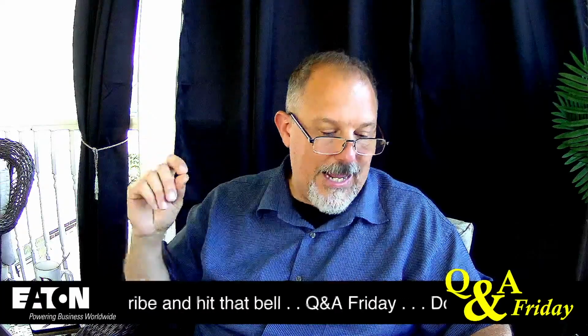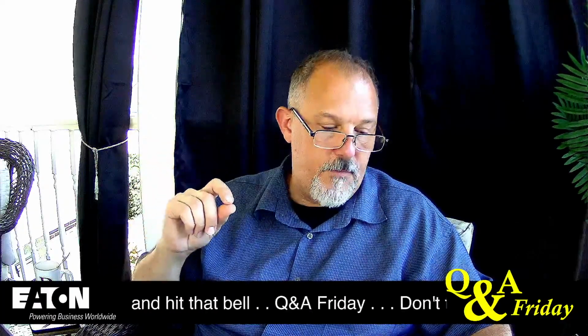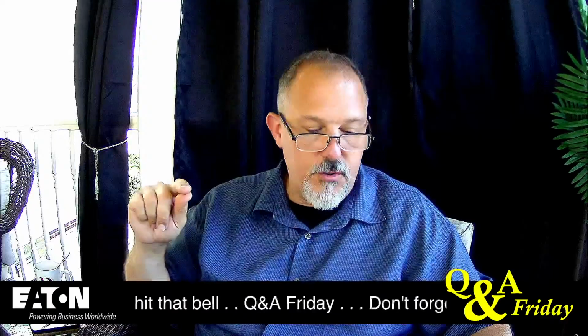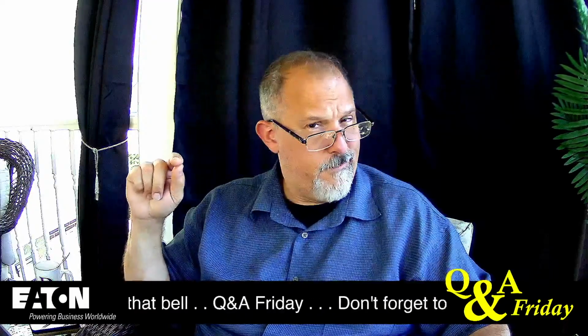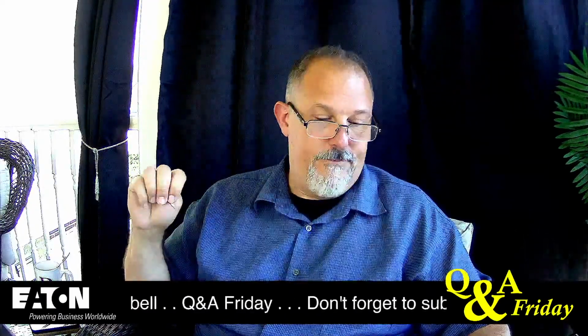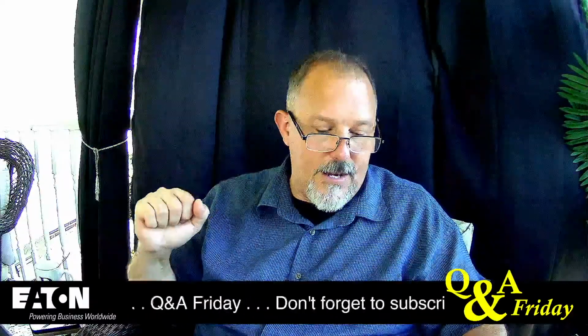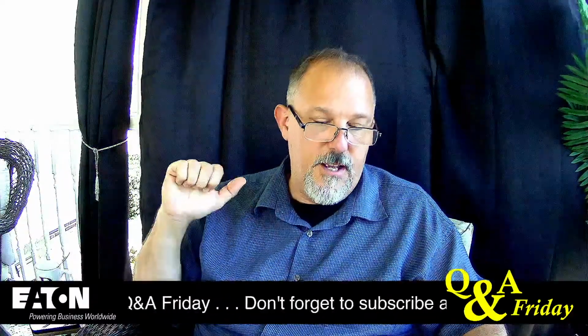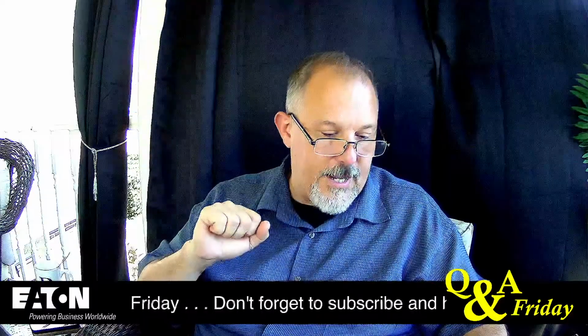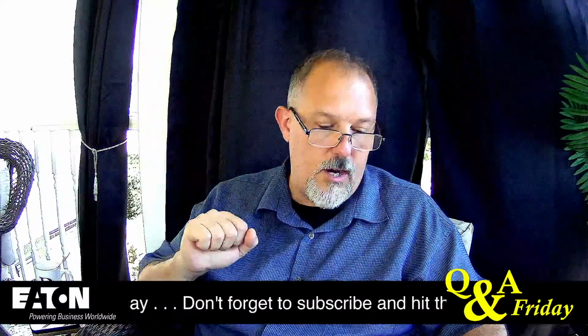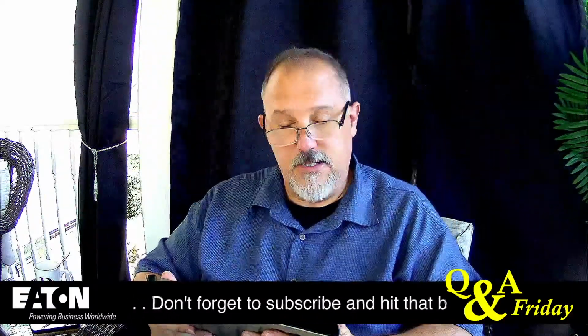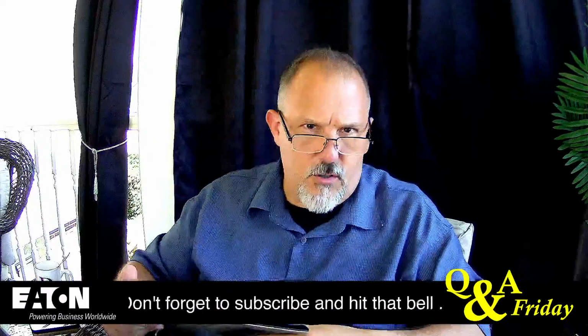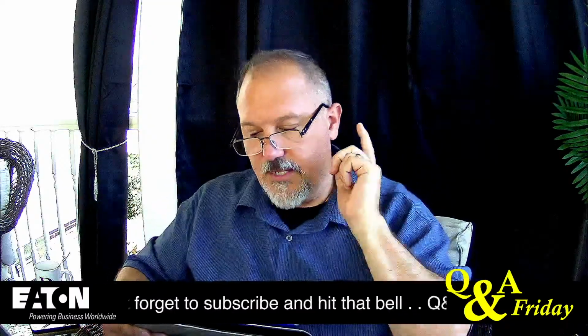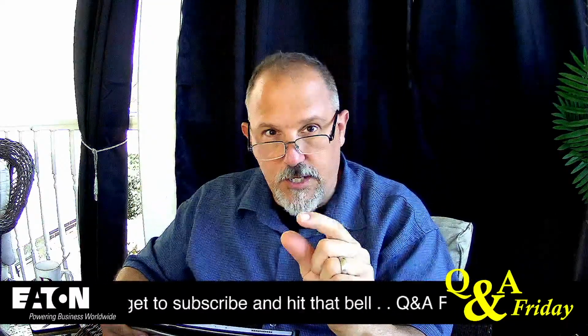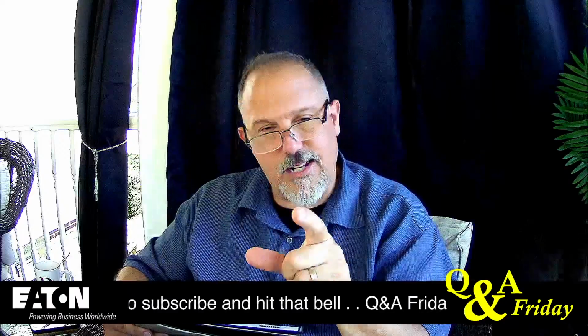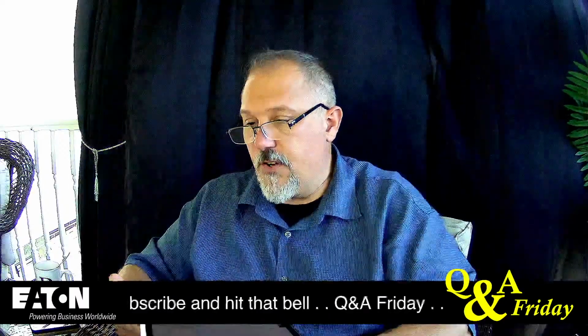When interrupting asymmetrical current, he says there's never a true zero crossing. So a higher system voltage means a higher voltage that the breakers will be interrupting at, which gets worse with more operating voltage. All right, so I'm not sure I completely agree with everything he said, but both of these questions are, I would say, somewhat related.